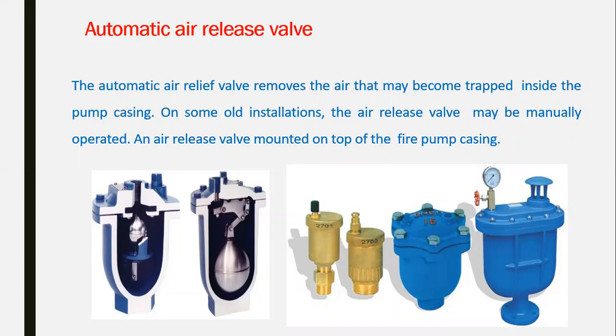This is the automatic release valve, and it has different shapes depending on the pressure, depending on the network, etc. The function of this automatic relief valve is to collect the air and take it out of the network. It removes air that may become trapped inside the pump casing. In old installations, the air release valve might be manually operated, mounted on top of the fire pump casing or on the common header. By nature, air goes to the highest point, so you have to select the automatic air release at the highest points where you have accessibility to release the air from the network.